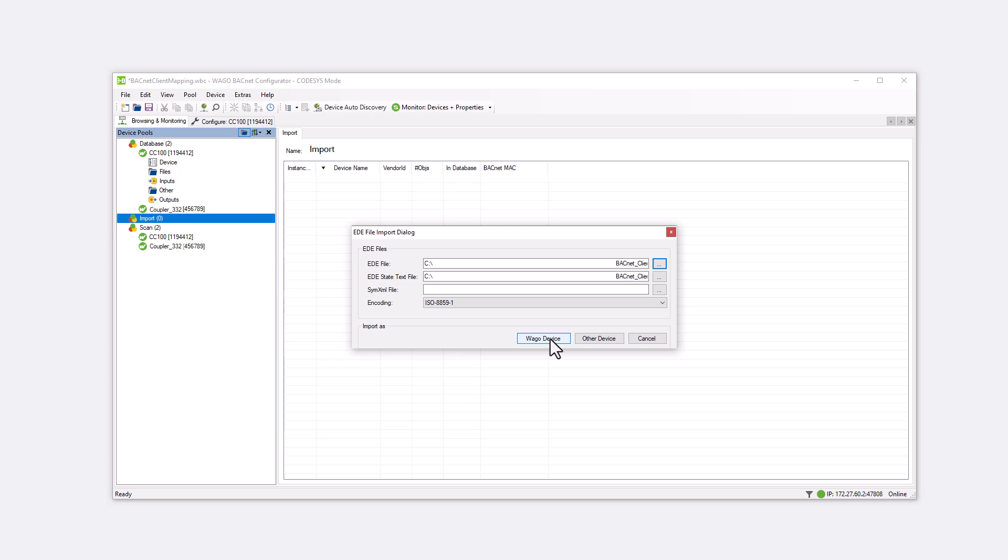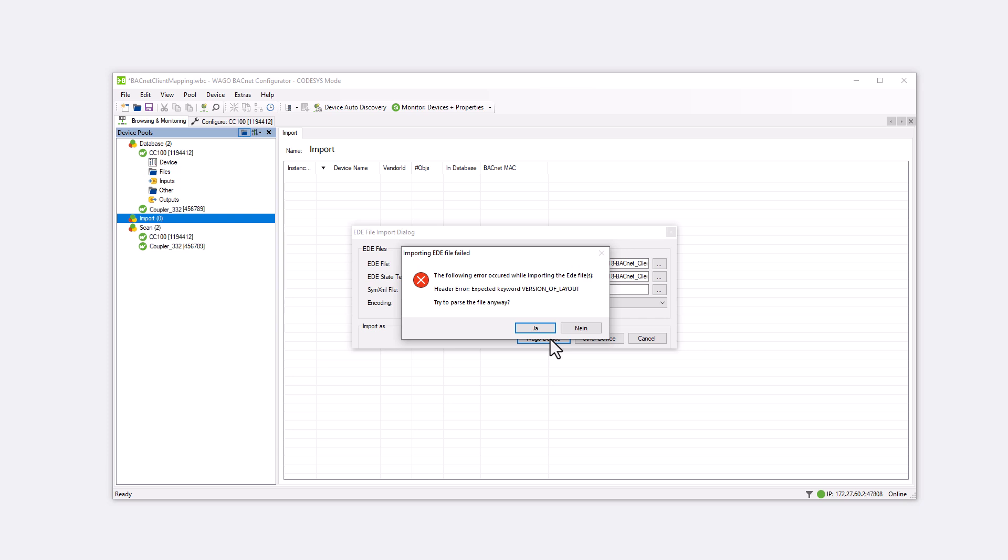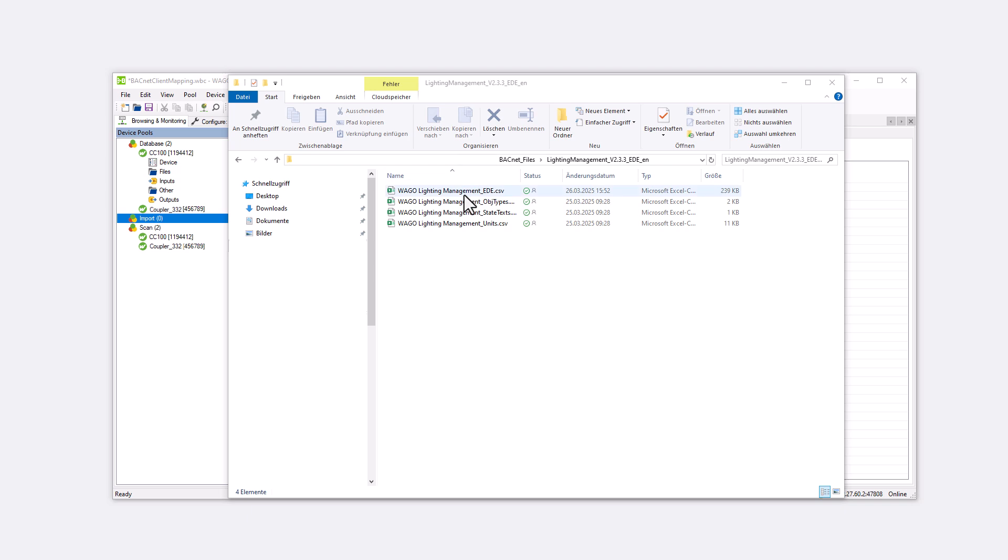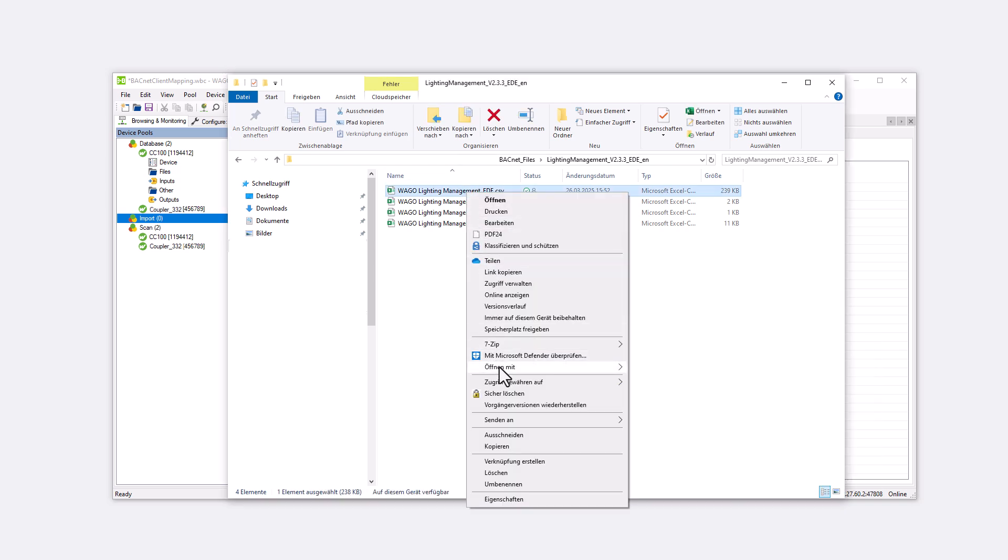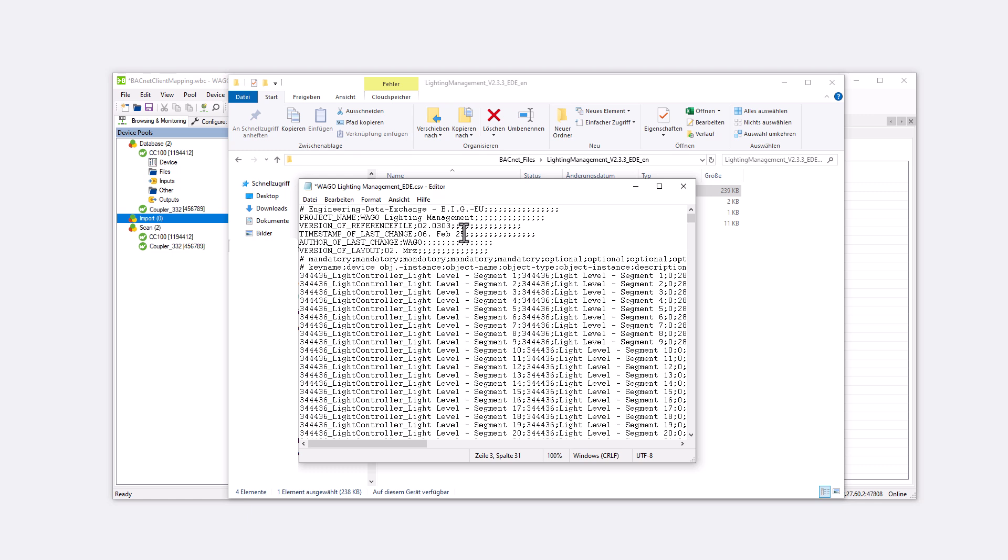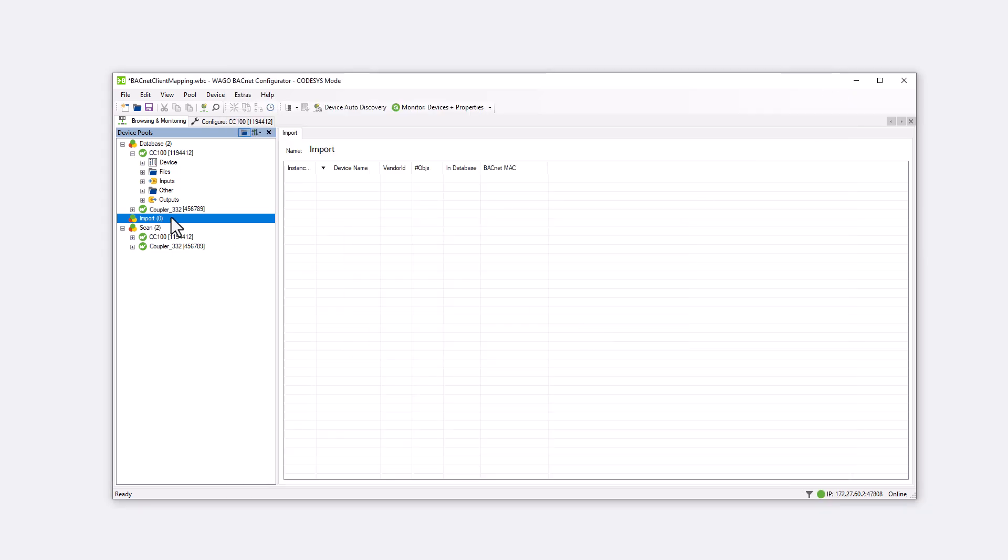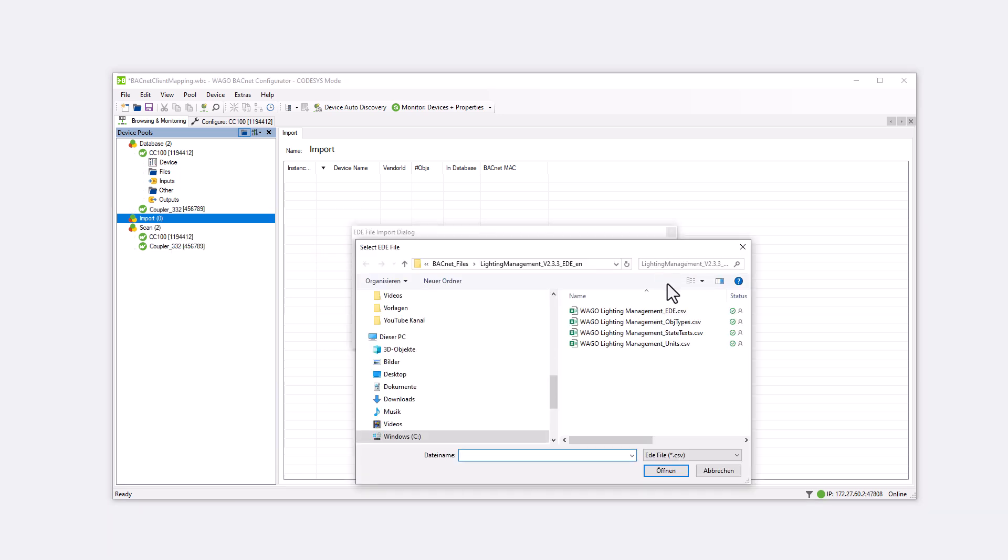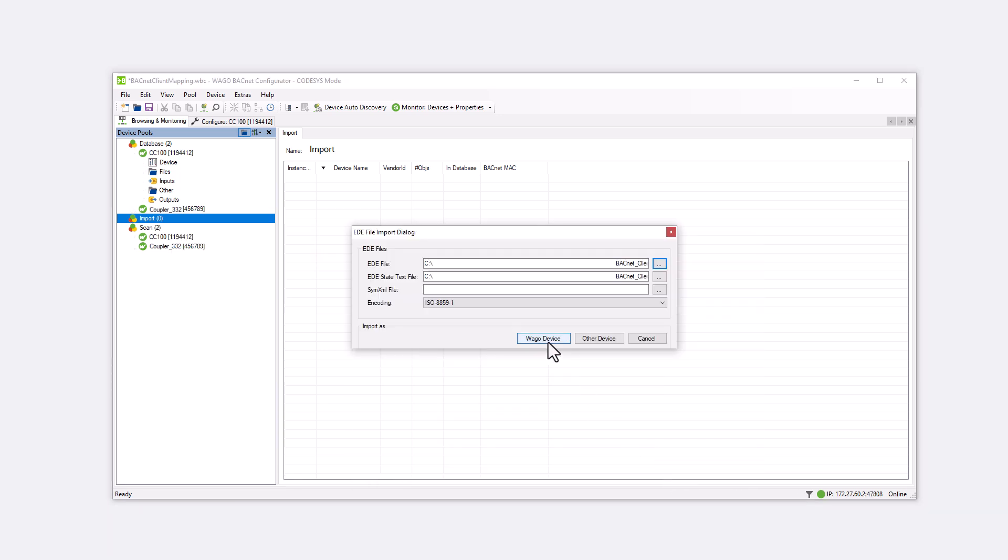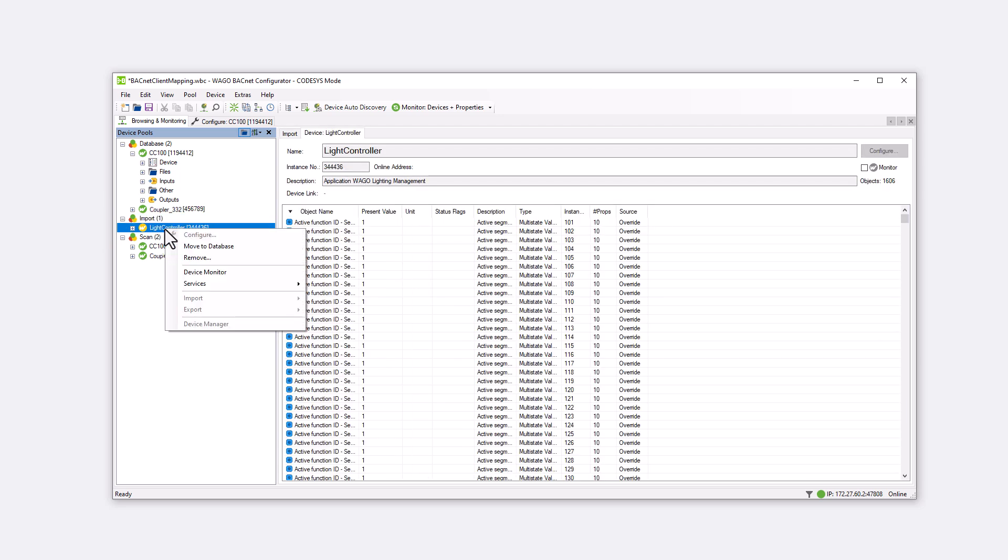An EDE file from another manufacturer would be imported as other device. However, now the error message header error expected keyword version of layout appears. This error typically occurs when the CSV file was previously opened with Excel. Excel interprets the version number as a date, converting version 2.3 to the 2nd of March for example. We open the CSV file with a text editor such as Notepad and change the version number back to 2.3. The import runs error-free and the device appears under Import. We can add it to the database with a right-click and then configure it as desired.